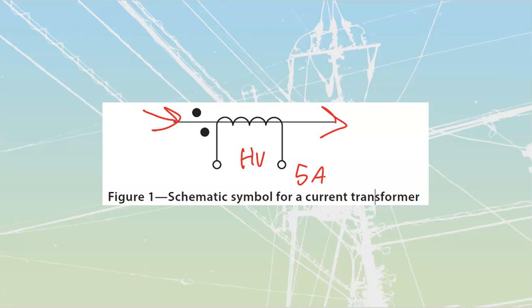They can actually go higher than 5 amps, but they're designed around this 5 amp class. Sometimes Hydro will, in their designs, put these in and give you something like a 400-5 transformer when you've got a 600 amp service. Don't worry, they've done the math. They understand it's going to be more than 5 amps, and that's fine. The transformer is able to actually do it.